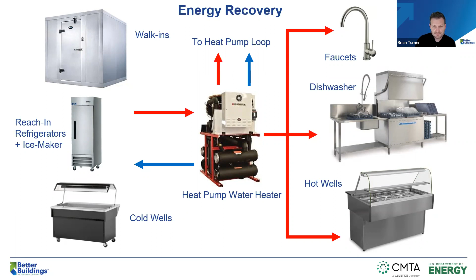Just to touch back on the potential sources of energy recovery, particularly with refrigeration, but not just with refrigeration. So most commercial kitchens are going to have a lot of refrigeration needs. So they're constantly rejecting heat. If you can reject that heat to a water loop where it can be recovered, that heat can be used for a lot of things, not just hot water at sinks, but it can feed the dish machines. It can even potentially feed the hot wells on the serving line. So you can sort of create this closed loop where the devices that need hot water and the devices that are constantly rejecting heat are just in a circular pattern, trading heat back and forth within the kitchen. Also helps reduce the number of geothermal wells or tonnage of cooling tower you might need outside to support the HVAC system.